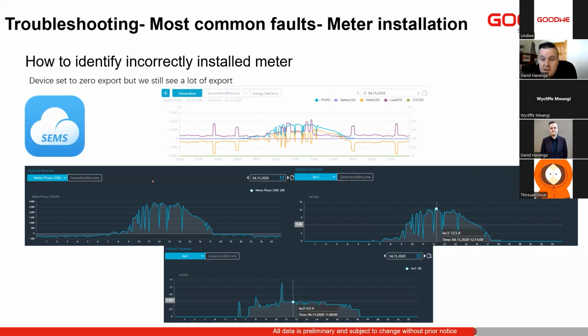So the first thing I did, I used the curve on the SEMS portal to find the meter phase that was showing me the export we are seeing. Then I went to IAC. So IAC is the AC output, the grid output of the inverter. I can see it on phase 2. The meter's on phase 2. On phase 2 on the inverter, we have no power really coming out. But on phase 3 of the inverter, we see all the power, which matches the export power on the graph.